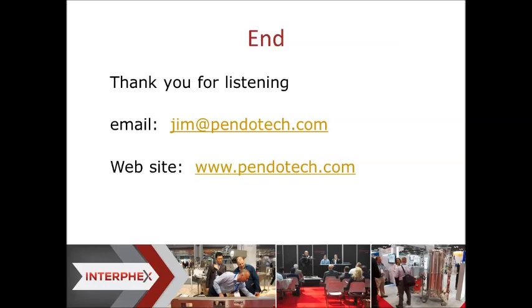Nothing right now. A number of years ago, we were working with a couple companies. We molded parts, and instead of putting the optical detector on a bioreactor bag, we put it into our flow cell. We made an adapter where the material could be exposed, and the response time was very slow, because with electrochemical probes for pH, it's almost instantaneous when you see a shift. And a lot of processes with inline processing, you're looking for a very distinct rapid change. And it was just too slow. And also the range is more narrow. In a bioreactor, you typically want to maintain about a neutral pH, whereas in downstream processing, you might be going down to 4 and looking for shifts. So it didn't give us the accuracy, the range, and the response time that was required. I don't know if a whole lot has changed in the pH area, but we're keeping in touch with some companies in case that changes.